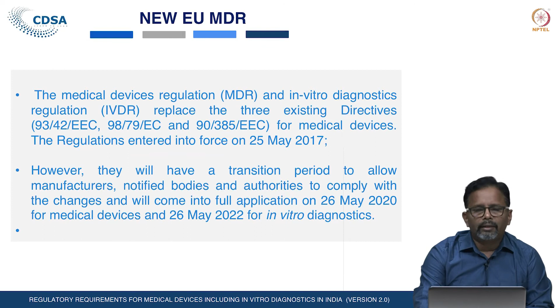This new regulation entered into force on the 25th of May 2017. However, a certain transition period has been given to manufacturers, notified bodies and authorities to comply with the new changes of the law, which will come into full application on 26th May 2020 for medical devices and 26th May 2022 for in vitro diagnostics. Three years for medical devices and five years for in vitro diagnostics have been provided for implementation of this regulation in the European Union.